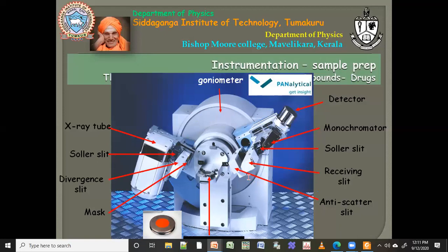In some cases, like a tabletop diffractometer, the X-ray tube is fixed, and the sample and detector move in one single arm. That is only for a few cases, mostly tabletop. In any case, you will have theta-2 theta movement, which is how you change the theta.